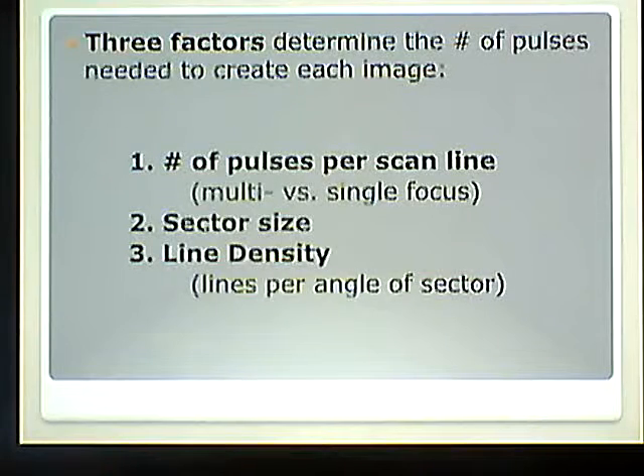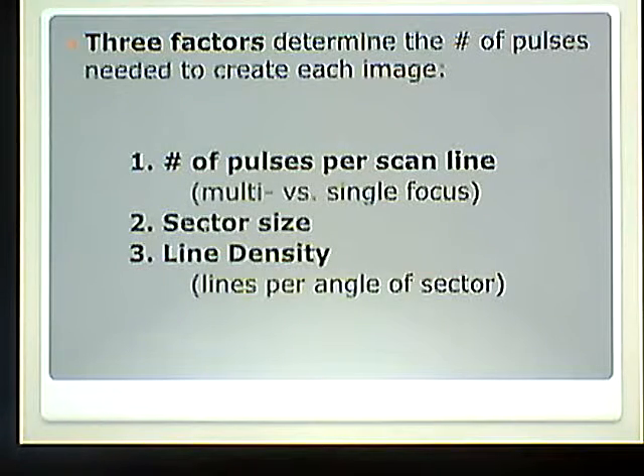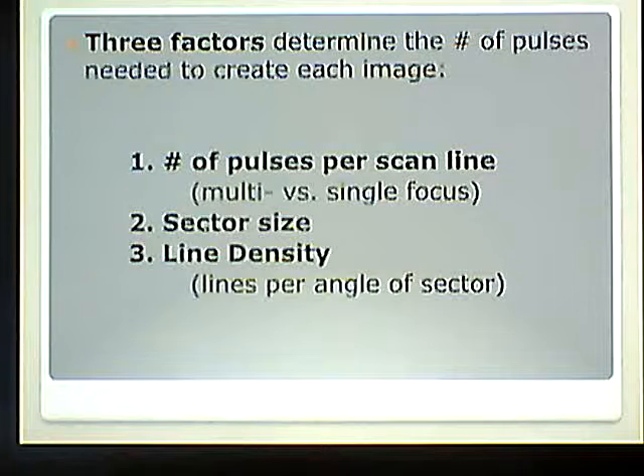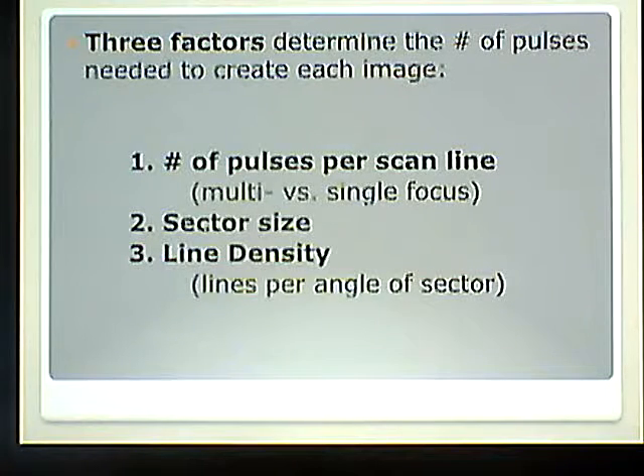All of these things we're doing add pulses to the image, therefore increasing the time it takes to make each image, therefore decreasing the frame rate or the number of cycles made per second, therefore decreasing temporal resolution. It always goes back to how long it takes to make one frame — and then the domino effect happens.